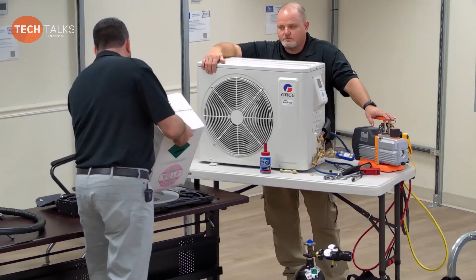Because we want to push liquid in. Now, at this point, after you've verified that your vacuum is correct, you can go ahead and weigh those few ounces back into the system. The vacuum is going to pull it in. Yeah, so you shouldn't have a problem trying to force the refrigerant into the system.